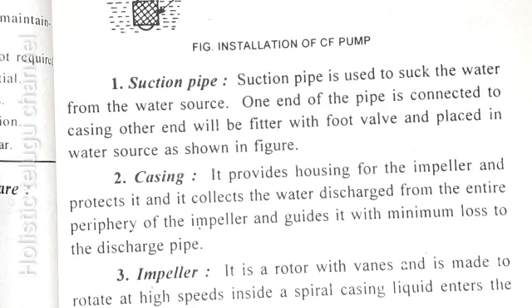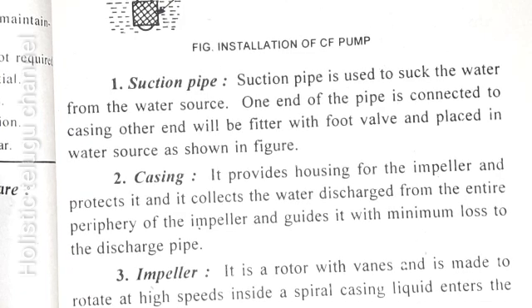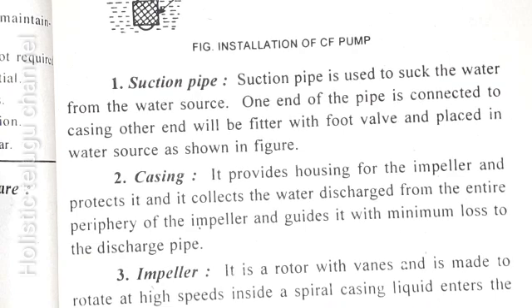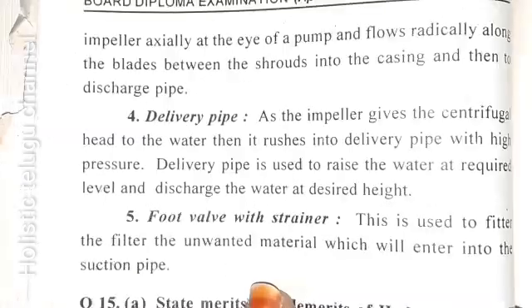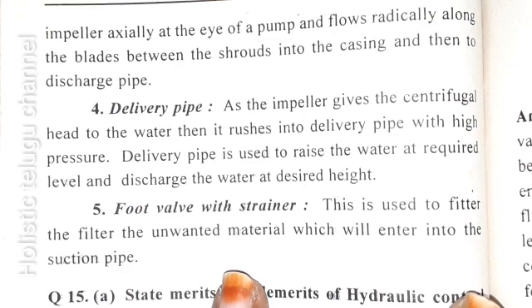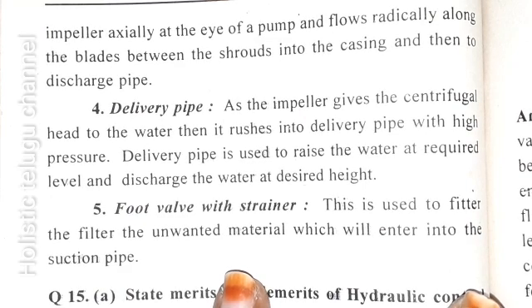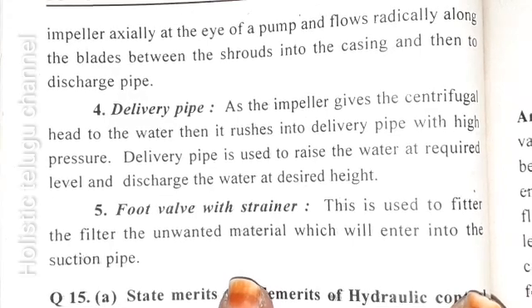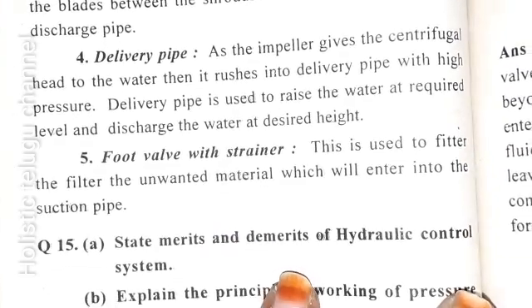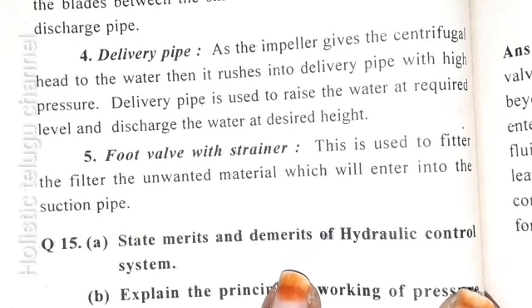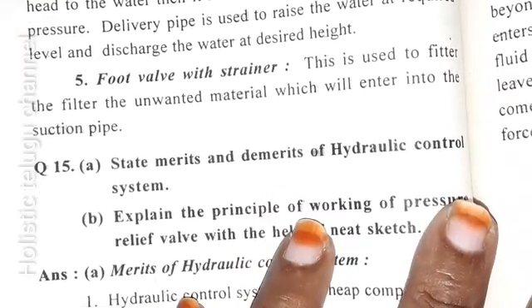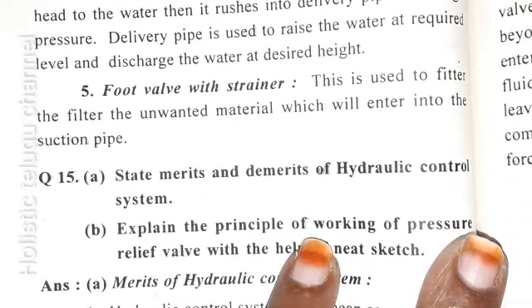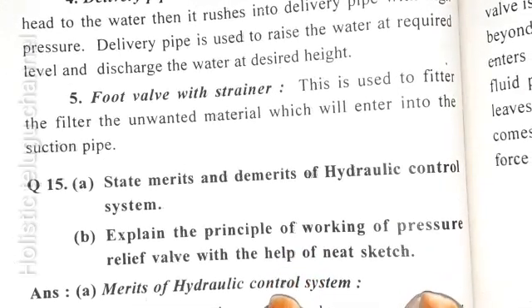Casing: it provides housing for the impeller and protects it. It collects the water discharged from the entire periphery of the impeller and guides it with minimum loss to the discharge pipe. Impeller: it is a rotor with vanes and is made to rotate at high speeds inside the spiral casing. Liquid enters the impeller axially at the eye of the pump and flows radially along the blades between the shrouds into the casing and then into the discharge pipe. Delivery pipe: as the impeller gives the centrifugal head to the water, it rushes into delivery pipe with high pressure. Delivery pipe is used to raise the water at required level and discharge the water at desired height. Foot valve with strainer: this is used to filter the unwanted material which will enter into the suction pipe.